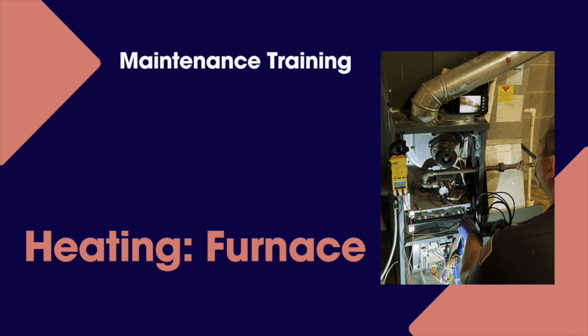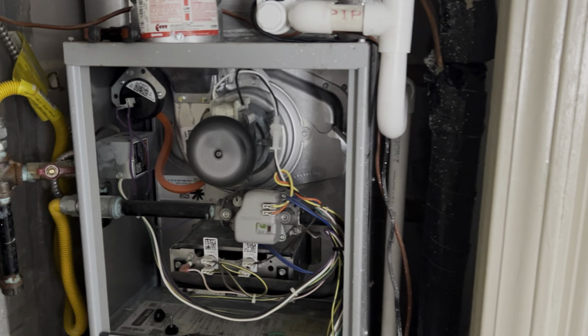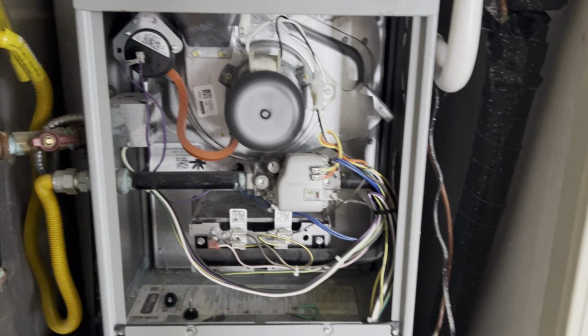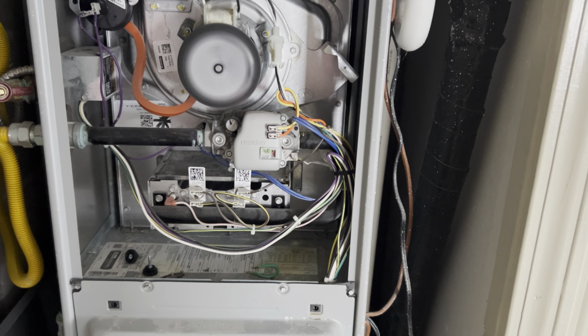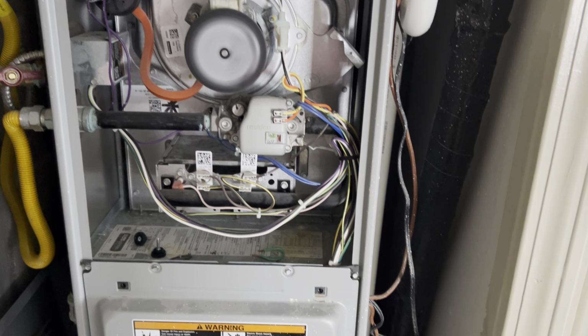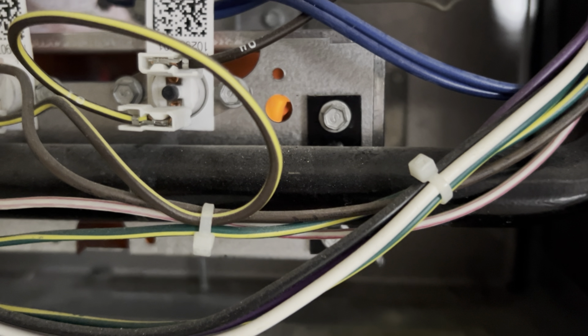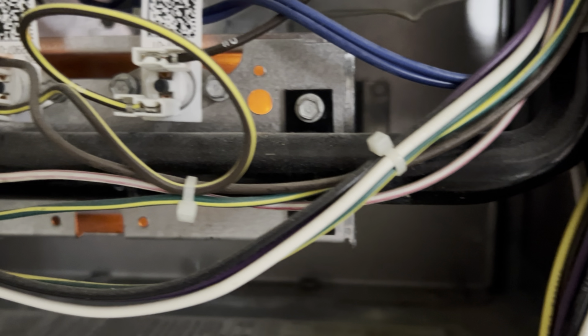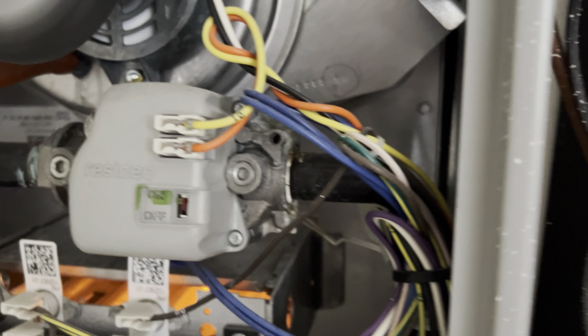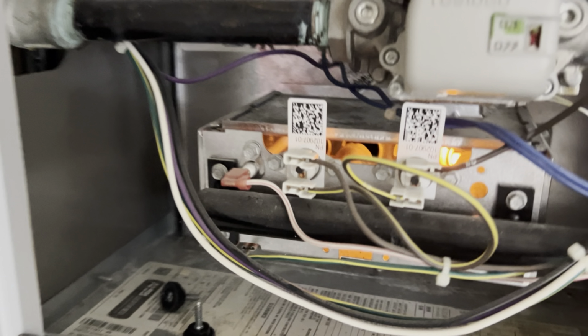The last section is heating. In this case, we have gas furnaces. The inducer fan motor is the first thing to turn on, and it's the thing I'm pointing at here with my laser. Once the fan proves airflow through the pressure switch, the igniter glows bright cherry red as it's energized. It is only held by that one screw back there, and it's mounted directly in line with the burners.